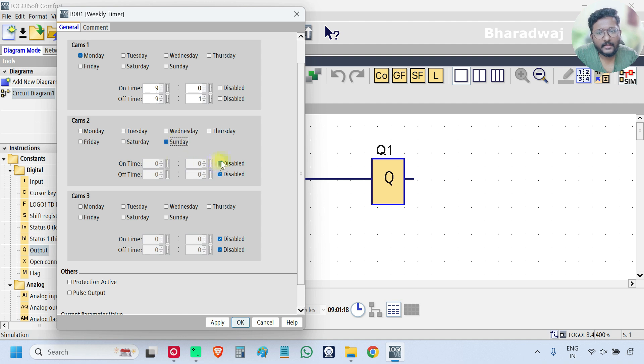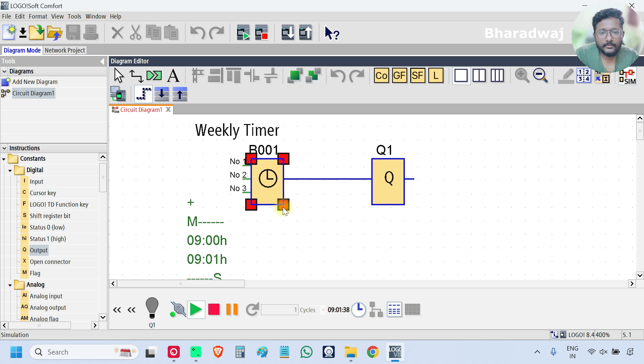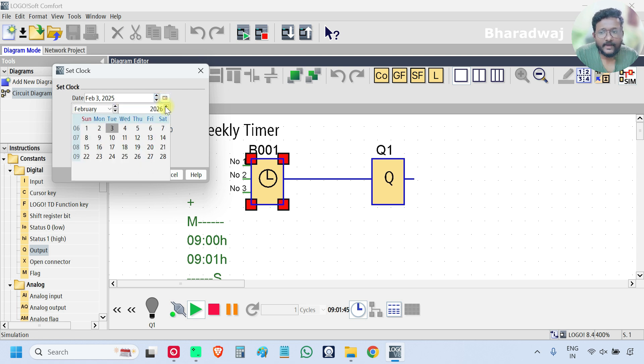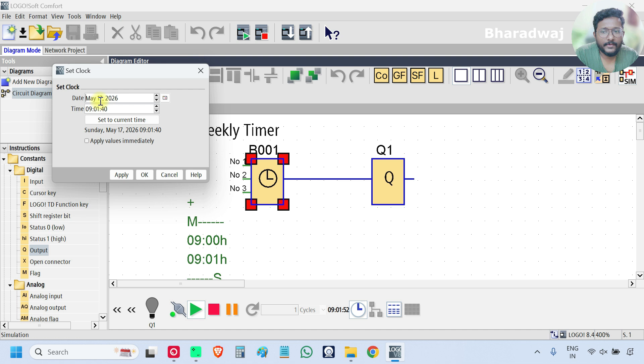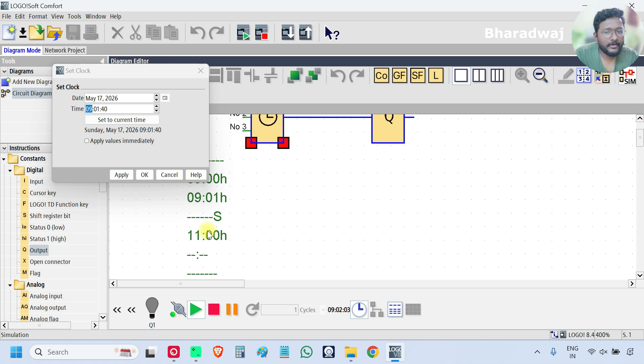On every Sunday at 11 o'clock, I want to turn on an output. But I don't need any off time — I just need continuous on. So at 11 o'clock my output will be turned on. Now, change the day. I will use 2026 and I will see May Sunday 17th. So 17th May 2026, it is Sunday — at 11 o'clock the output will be on. Off time is not mentioned, that means continuous on.